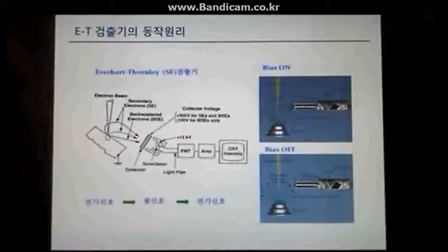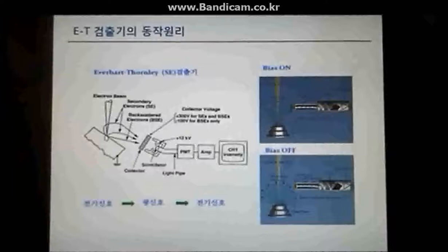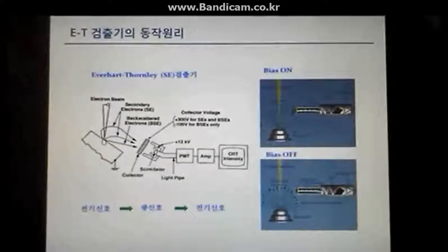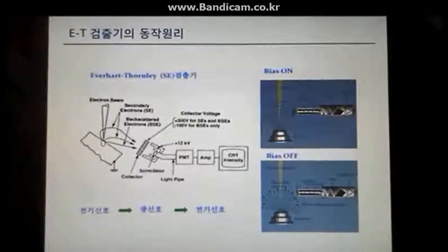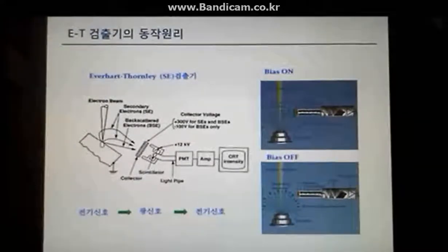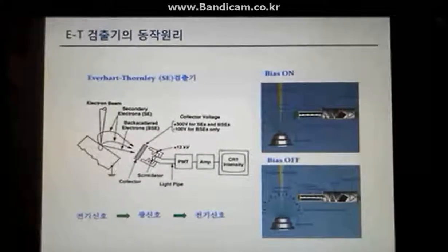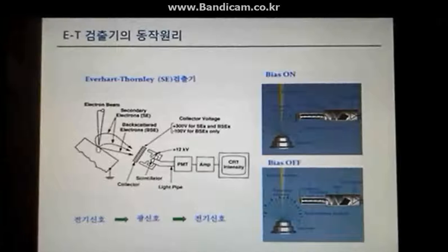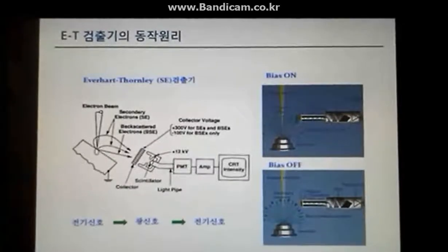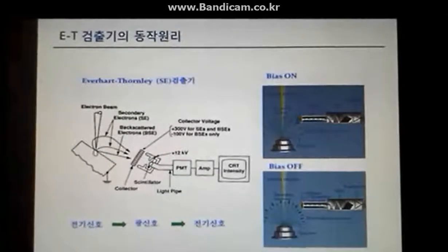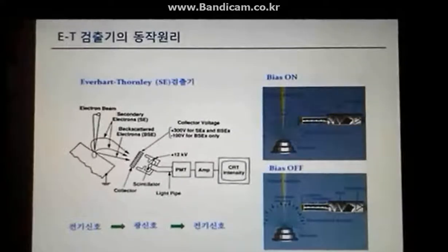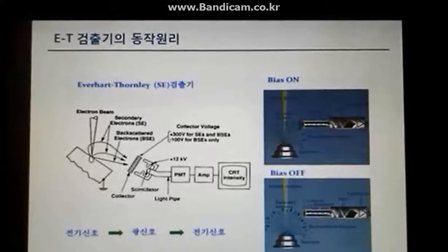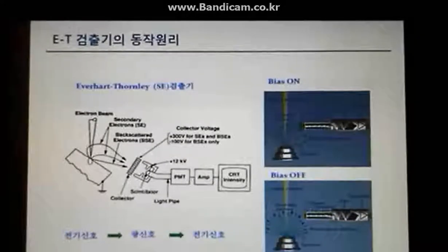According to the secondary electron detector: SE itself has a negative charge and spreads out in all directions. To increase the collecting efficiency of SE, the SE detector has a positive charge at the front of the detector, and the scattered secondary electrons are drawn toward this positive charge. This electron signal is then converted to a light signal through the detector, and the light signal is amplified and converted to an electric signal. The quantity and brightness of these signals determine the black, white, and gray levels on the screen.